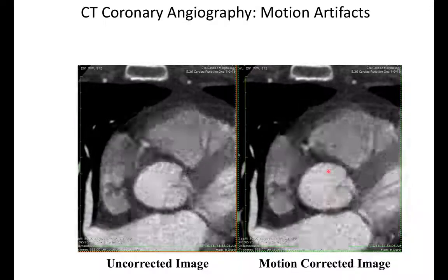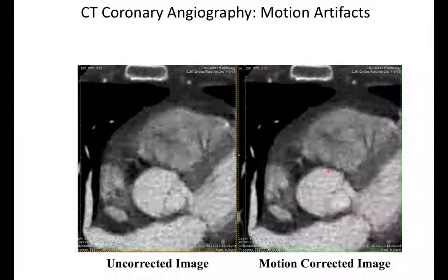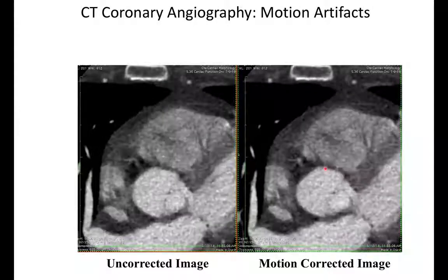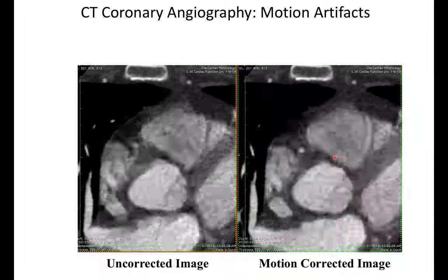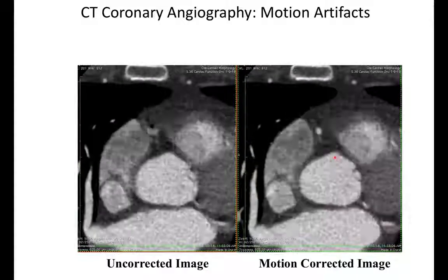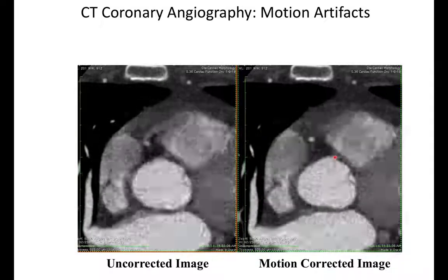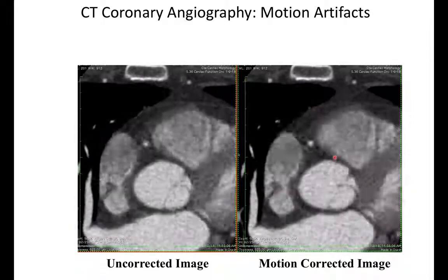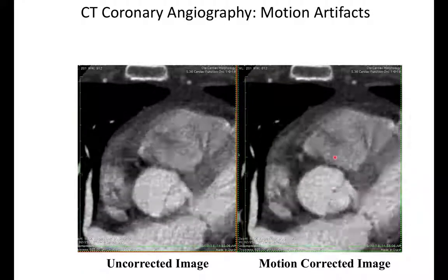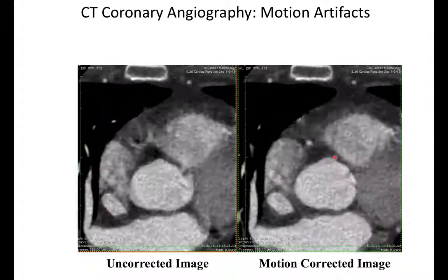This is what it looks like if you use a method that reconstructs the image under the assumption that this thing is moving. So you can correct your sinogram data in order to model the underlying motion. So you say, okay, if I have a disk and I take my sinogram data and look at it, that's one thing. Now if I have a disk that's moving linearly across the field of view, what does that sinogram data look like? It's quite different, right?